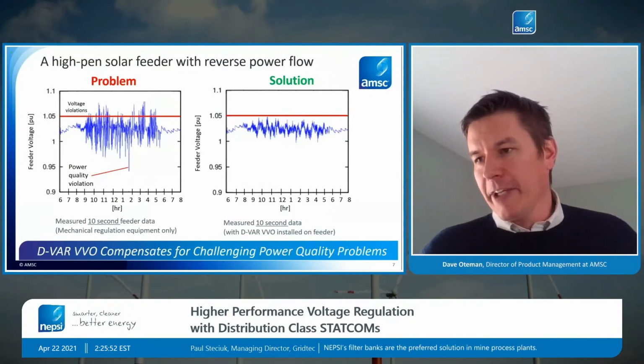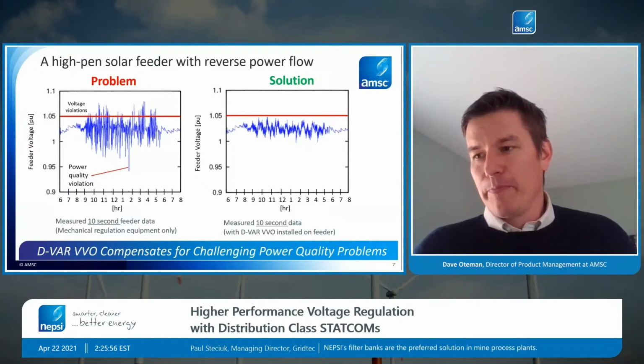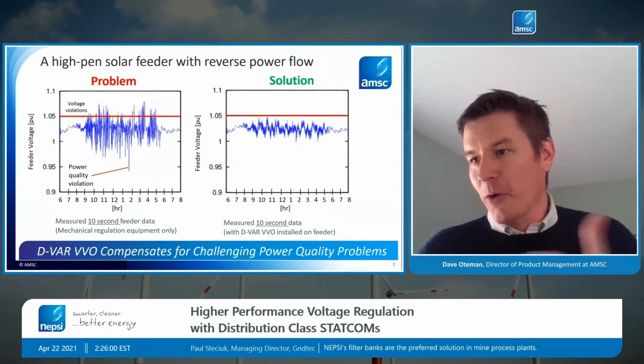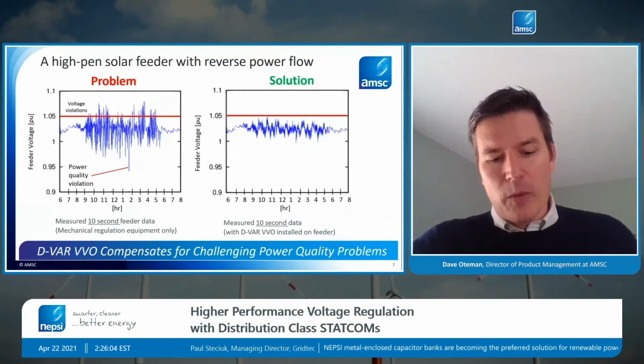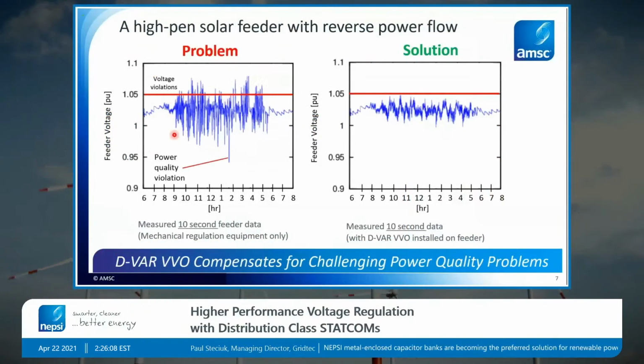Here's a waveform on a feeder that's highly saturated with solar, just to show some intuition as to these power quality problems. I showed the 8 power quality problems, and this has a bunch of them on it. What's shown on the left is this feeder prior to mitigating these voltage issues, during a spring day with significant net reverse power flow due to the solar generation. It's also a partly cloudy day. Before the clouds come in the morning, there's not so much of an issue. Then the solar resource is fluctuating by megawatts on this feeder and driving these voltage violations. We can clearly see the high voltage at full output, as well as sudden dropouts due to the cloud pass, rapid voltage changes that are considered violations as well.